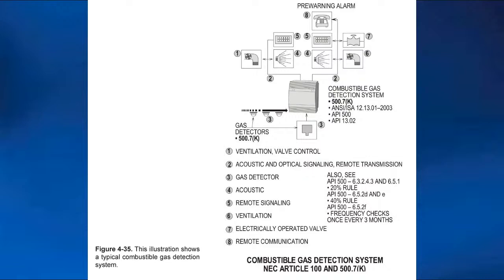And then, of course, the API says frequency checks on gas detection systems should be every 3 months. And if you guys ever look at 70B, the maintenance standard for electricians where you do maintenance, all you got to do is look at Annex L, make note of it. Annex L to 70B will give you all your frequency checks, your inspection procedures, and refer you to the section that gives you additional information.